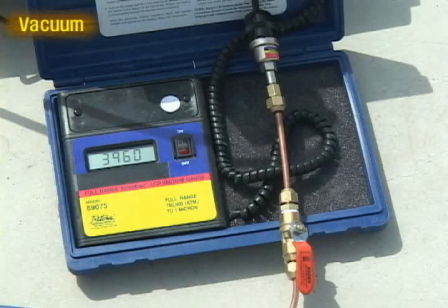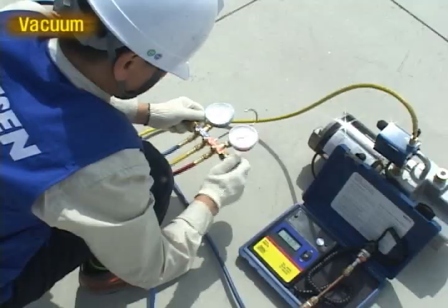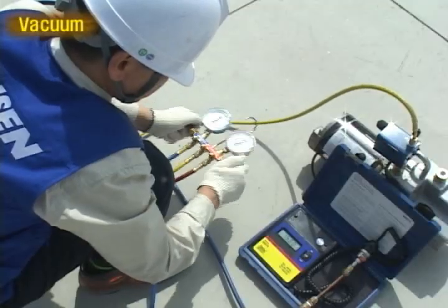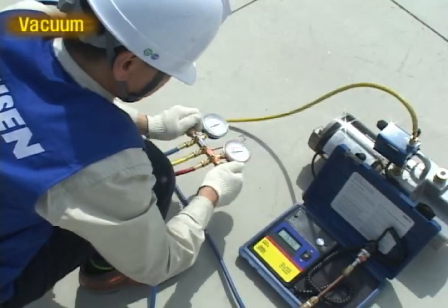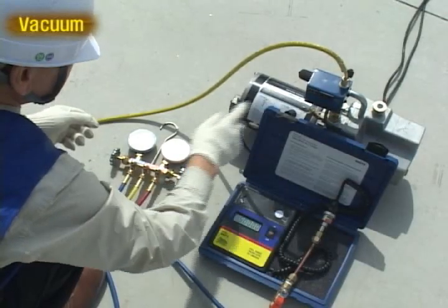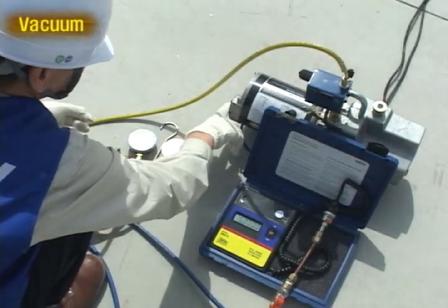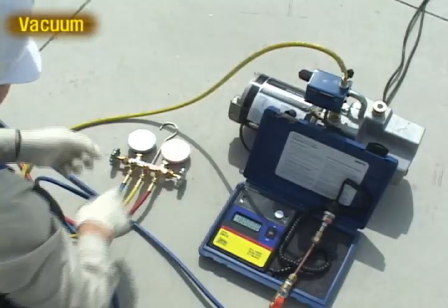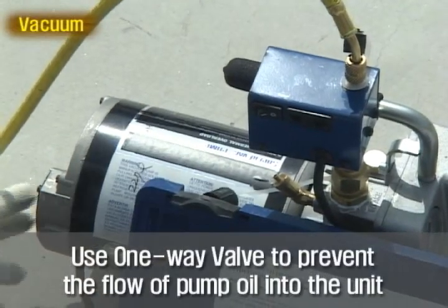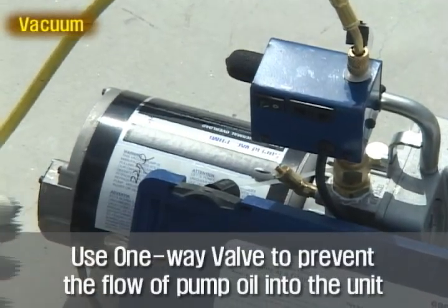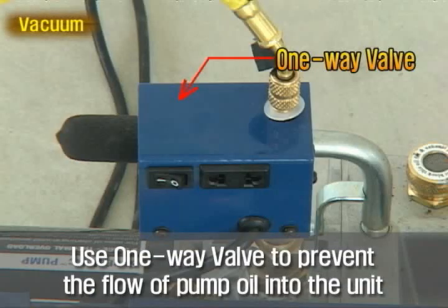After vacuuming, close the valve for 1 hour and check whether the vacuum is maintained below 5 torr or 5,000 micron without leakage. If the power supply is off during the vacuuming operation, or the manifold gauge valve is not closed before the power off, the vacuuming pump oil can flow into the product and cause damage. A one-way valve can be used for that.